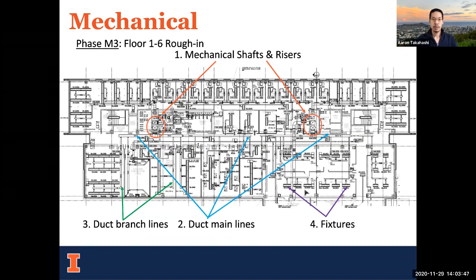Moving out of the basement is a bit unique because it has that specialized backbone equipment, which is only placed once in the building since it feeds the rest of it. On floors 1 through 6, the build-out starts with the vertical shafts and risers of the ductwork and piping. Then, on a given floor, once the shafts are in, you build out to your main branch lines, which in this case run over a hallway, typically to make them accessible to maintenance workers in the future.